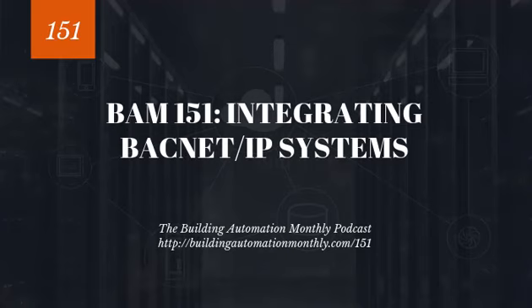Additionally, on top of the BBMD and BDTs that we need to get set up, and the unique device IDs and IP addresses, and the network numbers, we also need to make sure our ports are open. Typically, BACnet uses UDP port 47808 for its communication. All right, so that's a lot, right?